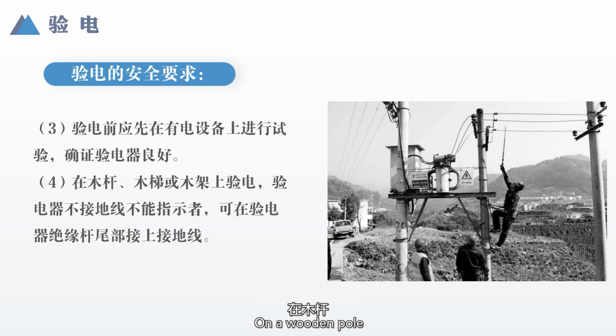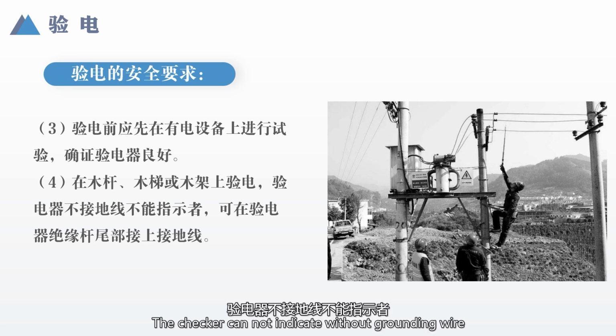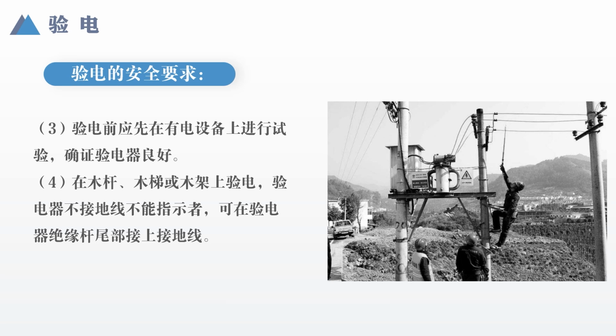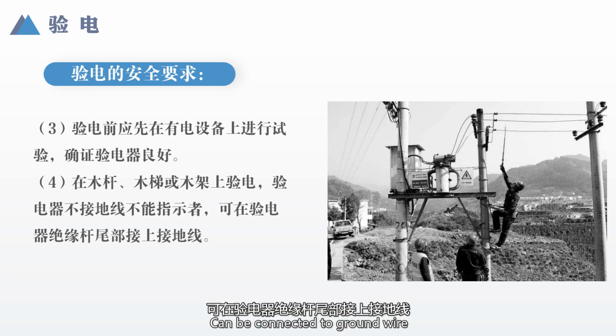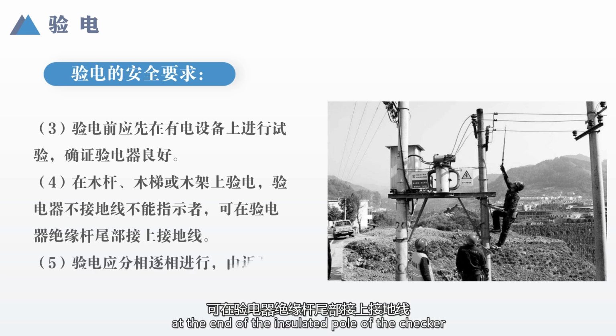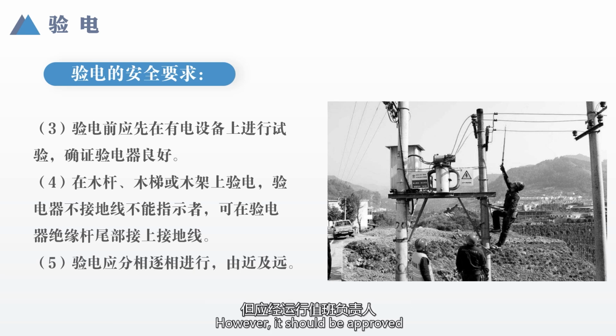On a wood pole, wooden ladder, or wooden frame, the checker cannot indicate without a grounding wire. It can be connected to ground wire at the end of the insulated pole of the checker. However, it should be approved by the person in charge of operation duty or the person in charge of the work. Power tests should be carried out phase by phase from near to far. Next, let's look at an accident caused by a violation of safety regulations.